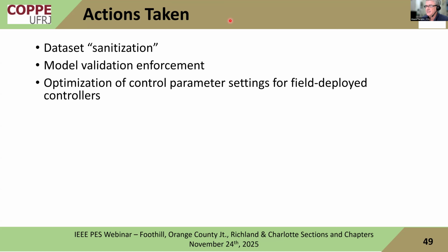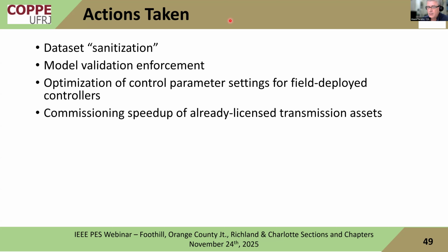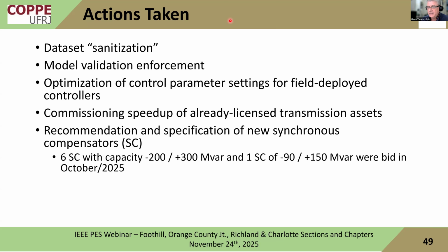Optimization of the control parameter settings for field deployment controllers. Also, many of the controllers were very slow in controlling the point of common coupling, and then they are optimizing some control parameters in field. Commissioning speed up of already licensed transmission assets. A recommendation and the specification of new synchronous compensators or new synchronous condensers. So 6 synchronous condensers with a capacity of minus 200 plus 300 megavars, and one synchronous condenser of minus 90 and plus 150 megavars were bid last month.